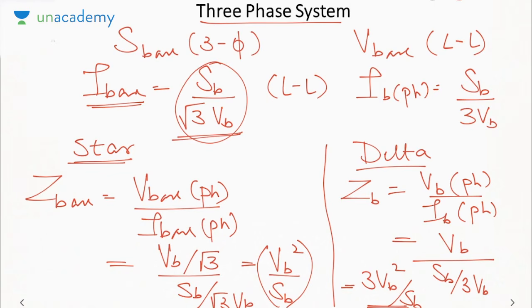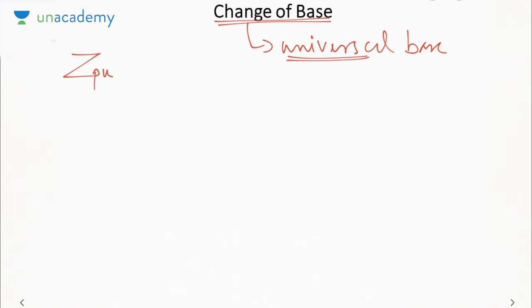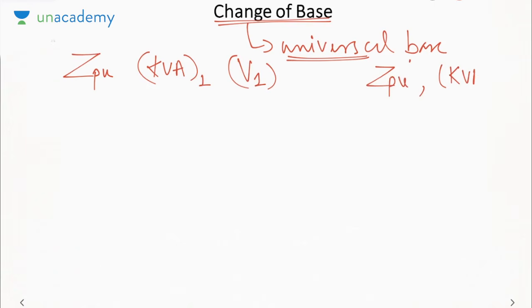For a three-phase system, you must assume line voltage as the base voltage and three-phase power as the base MVA. But now suppose impedance is given on one base and we need to find the impedance on another base. As I told you, we need to change the base to a universal base for the entire system. This is the most important concept from this chapter, that we have to convert the system to a universal base. Now suppose I give you a per unit impedance Z PU, which is given on a base of kVA 1 and V1. We need to find the Z PU dash on a base of kVA 2 and V2.